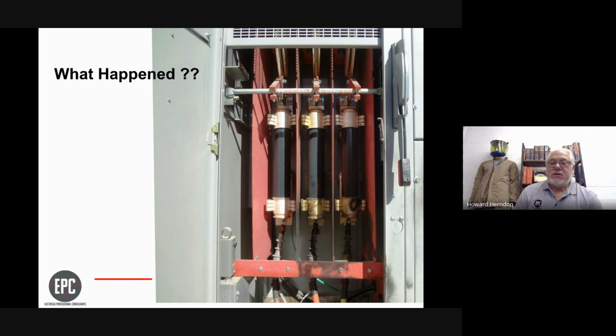Now, this switch is what we call a 5 kV rated switch. It's 4,160 volt. He'd been using the same meter all day. That meter was rated at 1,000 volts maximum. And there were plenty of caution labels on the outside of it. In fact, this gentleman had been involved in the installation of this system. One of the unique things about PV systems, or photovoltaic systems, is that oftentimes on the utility tie-in switch, one of these sides of the switch is always energized. And there's no standard that says it's the load side of the switch or the line side of the switch.